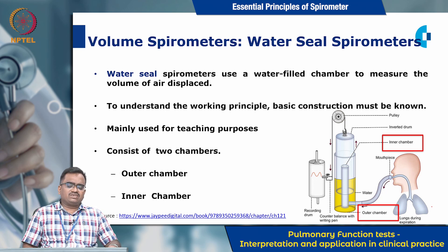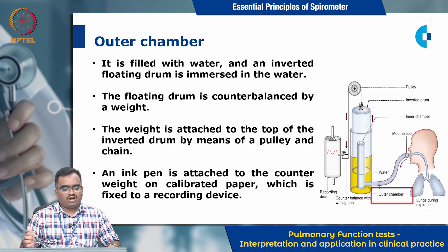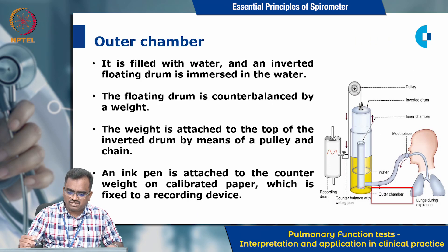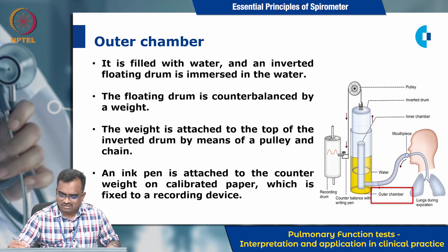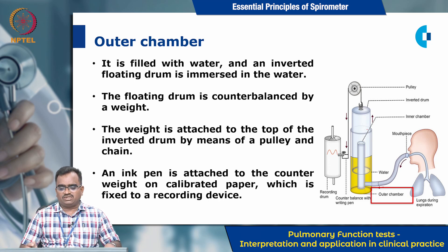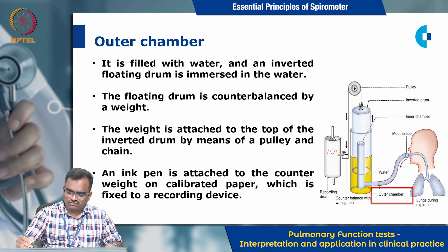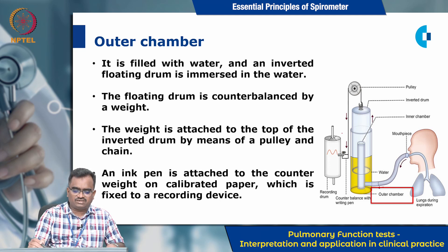The water seal spirometer consists of two chambers: the outer chamber and the inner chamber. The outer chamber is filled with water, and an inverted floating drum is immersed in the water. The floating drum is counterbalanced by a weight, which is attached to the top of the inverted drum by means of a pulley and chain.